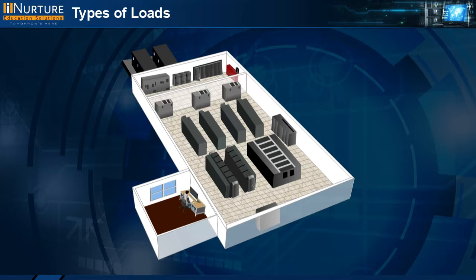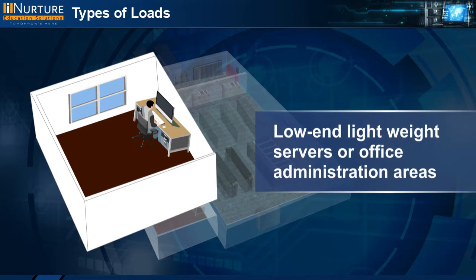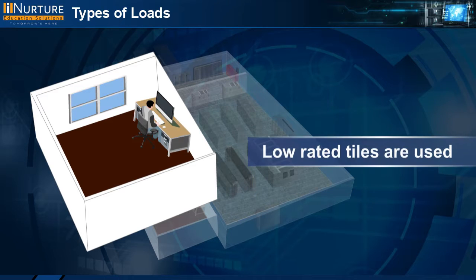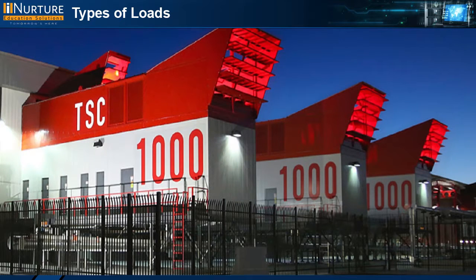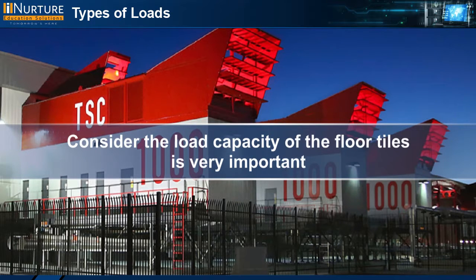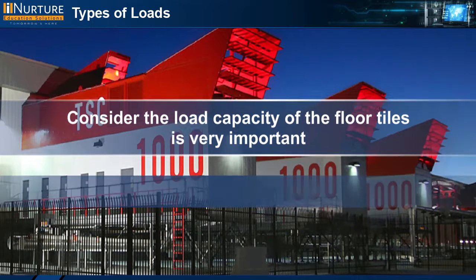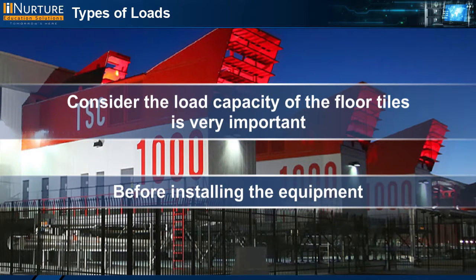The data center may have some areas that have low-end lightweight servers or office administration areas. Such areas can have low-rated tiles since they would not bear the load of heavy equipment. To conclude, it is expensive to replace floor tiles in a live data center. So, it is very important to consider the load capacity of the floor tiles before installing the equipment over them.